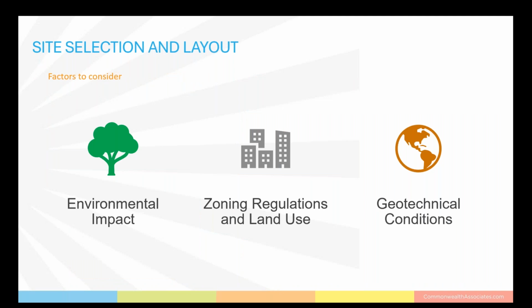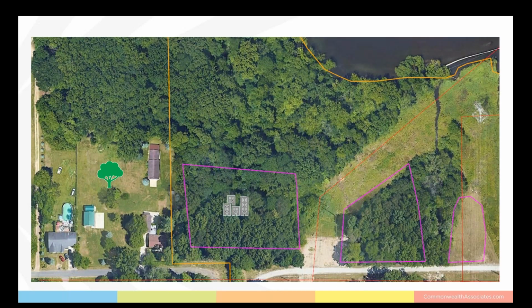Factors to consider on any site, whether it's new or existing: the environmental impact, zoning regulations and land use, and geotechnical conditions. In this example, covering environmental and zoning consideration, the proximity to the homes on the left relates to the environmental considerations, those being plant noise and potential hazardous materials like exhaust emissions, fuel gas, and if we're going to use ammonia for SCR, for example. Zoning considerations are to make sure that our site is simply zoned for the proper use. In this case, the purple box with the cartoon building is currently zoned residential, and we would need to rezone that with the county.